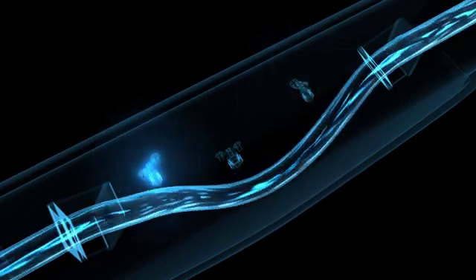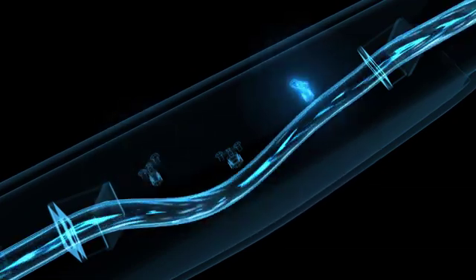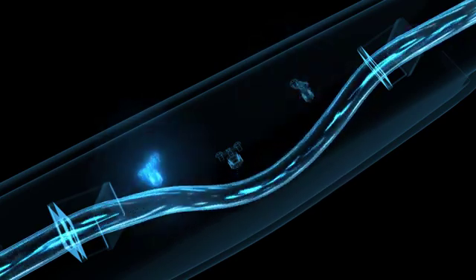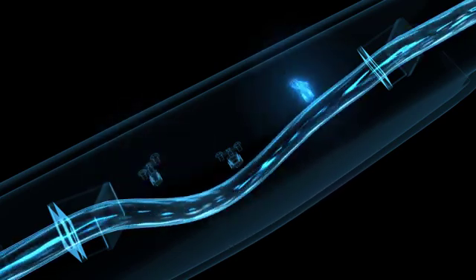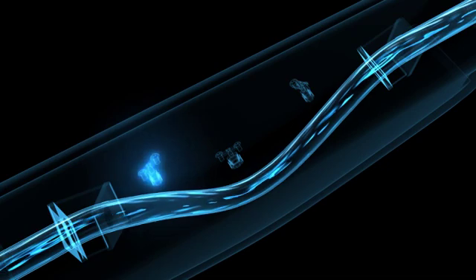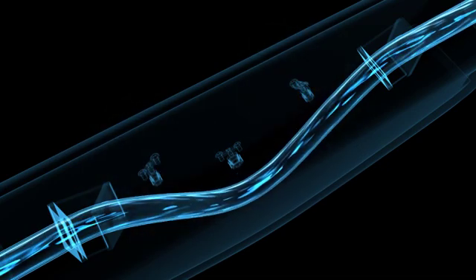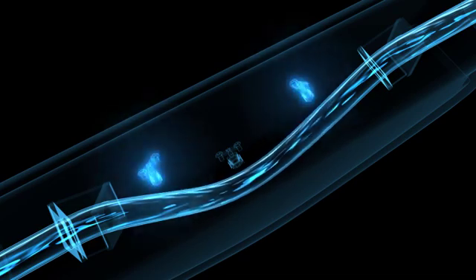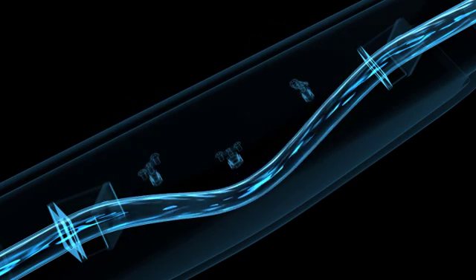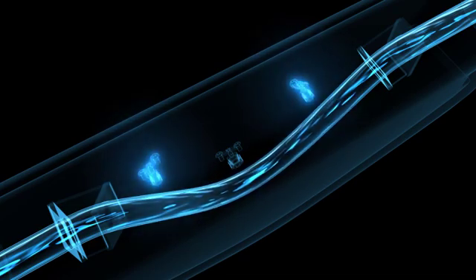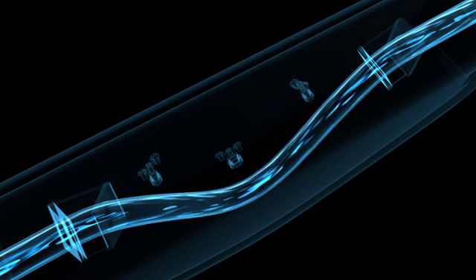The application of the Coriolis measuring principle doesn't stop here. It can also be used to simultaneously determine the density of the flowing fluid. To do so, the sensors also register the oscillating frequency. In other words, how often the measuring tube moves back and forth in one second.